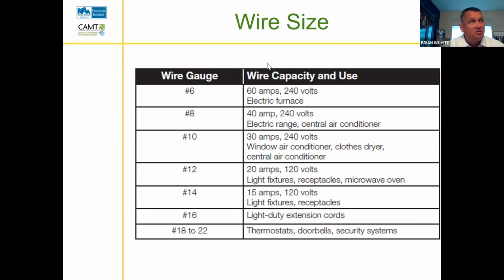So our power going to, let's say, our refrigerator is on a 20 amp circuit. They're using 12-gauge wire. Our lights and our electrical outlets, they're using 14-gauge wire. Our air conditioning units, 10-gauge wire. And then when we get into our secondary forms of electricity down here at the very bottom, our thermostat wire is usually 18-gauge, and it'll be either 18.2, 18.4, 18.5.